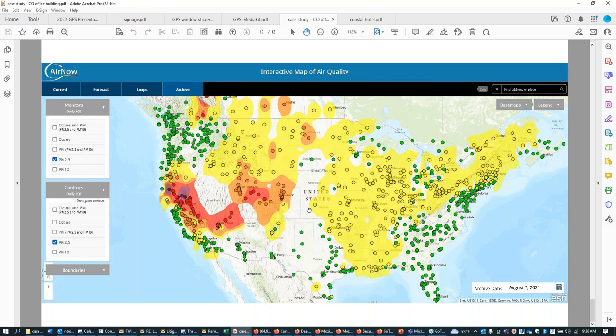And you know, it's bad enough to think about wildfire smoke as it relates to the airborne particulate related to the burning of forests and shrubbery. But think about when homes get consumed or when cars get in the path of these wildfires. Think about all the VOCs and the rubber and plastics and all the other things that get burned and they get aerosolized into the air and end up drifting across the country, and they end up in our buildings. And if you have that additional test data, not just CO2, but if you add particulate to what you're measuring, that's something that can be triggered to a building engineer to say, hey, something's going on. Your PM2.5 level has risen beyond your normal trend. Maybe you should turn off your outside air. Maybe there's an event taking place that you should basically isolate the building for a little while until whatever's happening is removed. So just something to be aware of and think about.